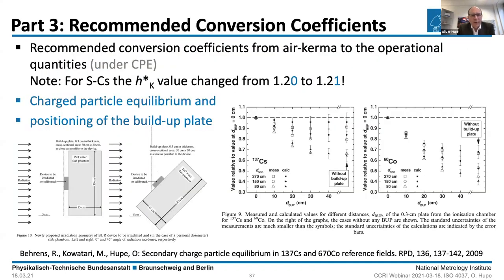The recommended conversion coefficients need charged particle equilibrium, what that is, and the positioning of the build-up plate. There's a publication; we made investigations on this, and we found out that if the build-up plate is far away from the dosimeter, and you have a dosimeter with a thin entrance window, you don't have charged particle equilibrium.